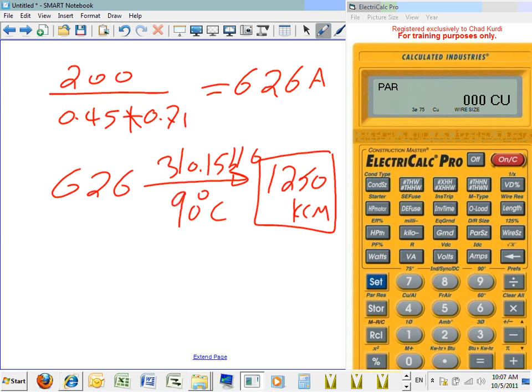We only carry it on branch circuits. They carry the harmonic. Harmonics are generated by ballasts and so forth. Now at a feeder level, the harmonics are minimized because you have air handling units and so many loads. So long story short, at the 2000 amp level, the harmonic will be mitigated by the nonlinear and linear loads together, and it's not an issue. Now, if you decided to make it an issue, you just change this one from 0.45 to 0.4, to account for the neutral.